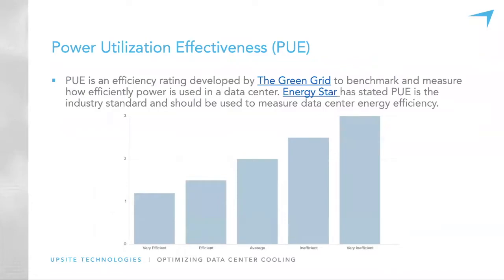During the Obama administration, they announced that all existing federal data centers should reach a 1.5 PUE by 2020, their target end date, and all new federal data centers opening needed to be at a PUE of 1.3. When looking at efficiencies and making effective use of the power coming into our facilities, I think 1.3 to 1.5 is more the range we look at now, whereas a few years ago, if you were at 2, that was considered pretty good.